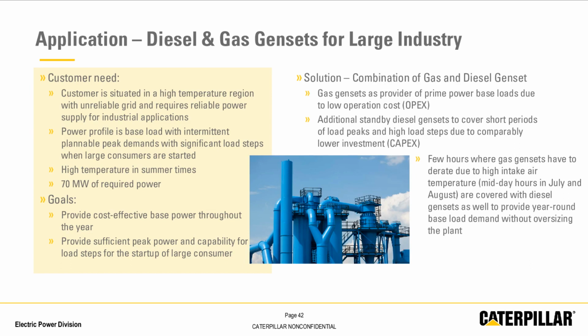This is when the gas gensets were derating due to high ambient temperatures, and would require the diesels to step in to make up for the gas derates. That's typical for a few hours every day in July and August. So the combination of separate gas and diesel gensets here was the optimal solution in this application, and there was no need for oversizing the plant.